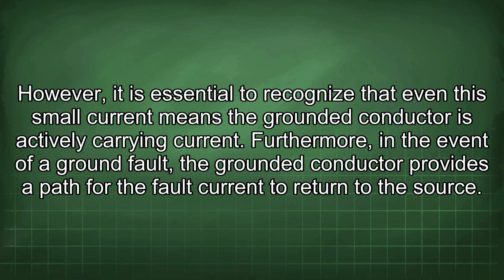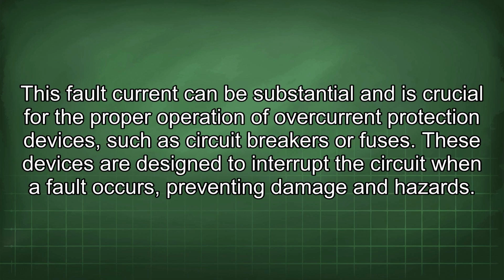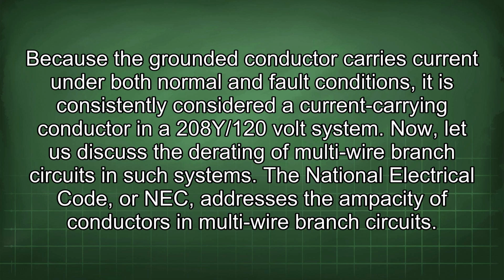Furthermore, in the event of a ground fault, the grounded conductor provides a path for the fault current to return to the source. This fault current can be substantial and is crucial for the proper operation of overcurrent protection devices, such as circuit breakers or fuses. These devices are designed to interrupt the circuit when a fault occurs, preventing damage and hazards. Because the grounded conductor carries current under both normal and fault conditions, it is consistently considered a current-carrying conductor in a 208Y/120 volt system. Now, let us discuss the derating of multi-wire branch circuits in such systems.